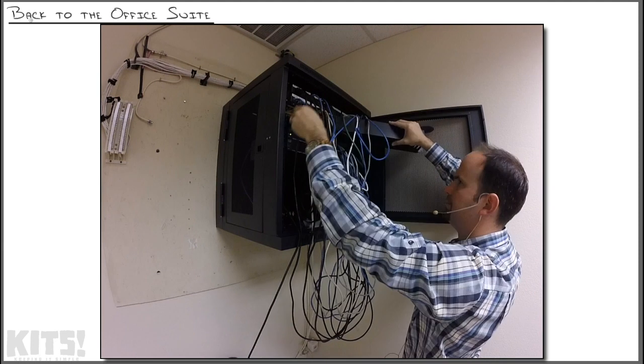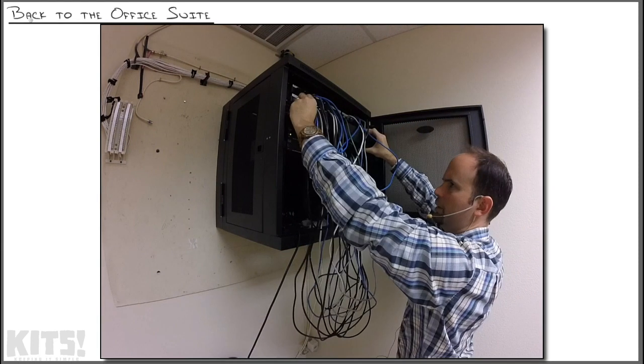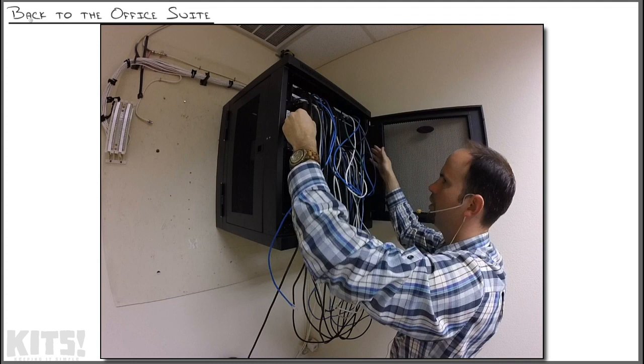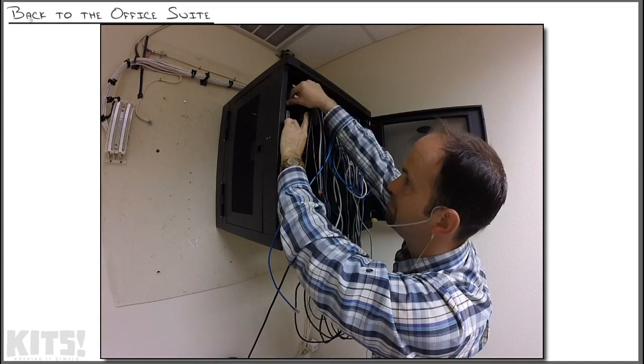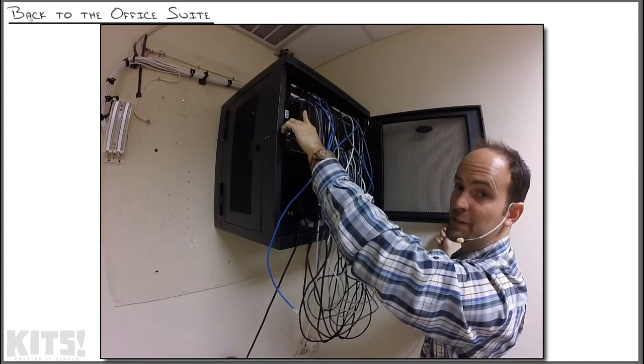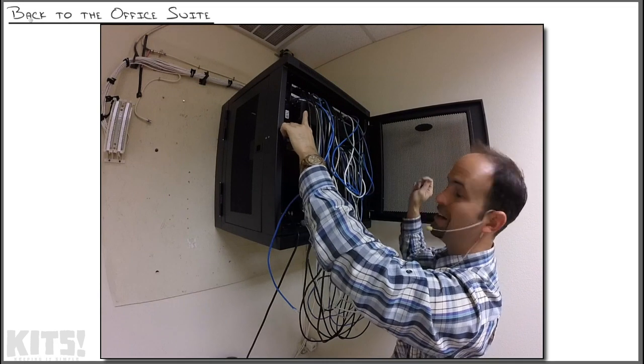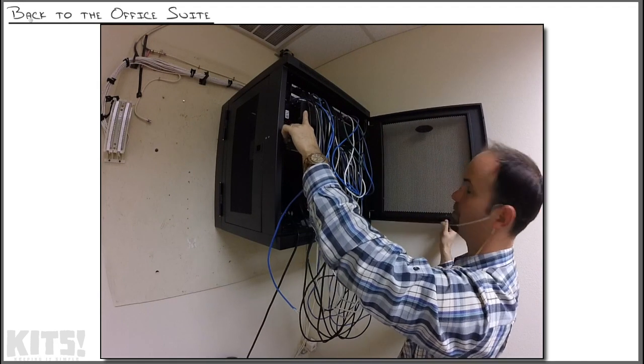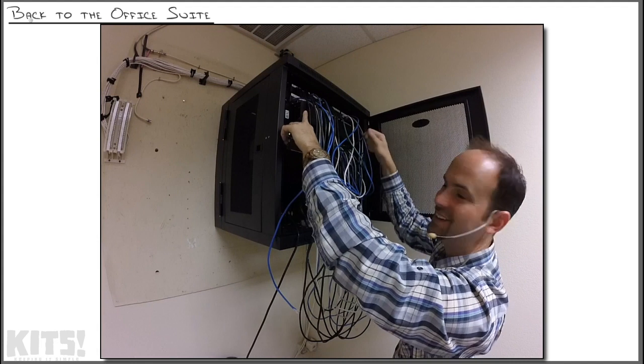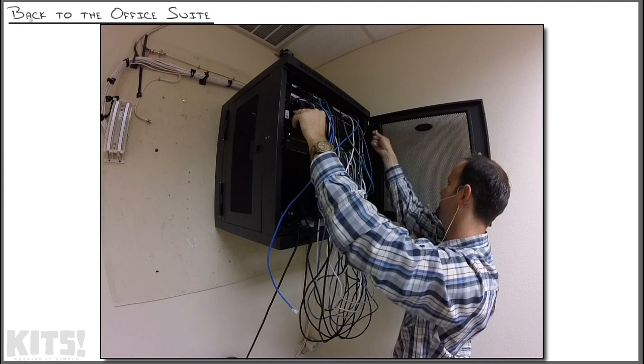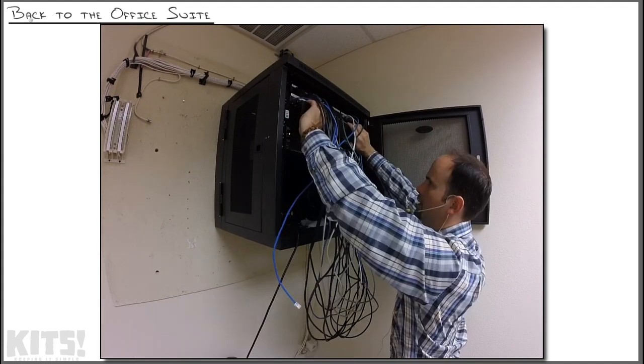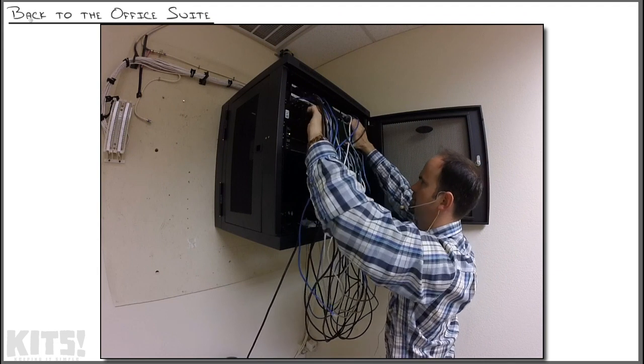Slide this guy in. I don't know what this little wire is doing here. There we go. Then we'll screw it in. You always want to make sure that your cable manager fits with the door closed. It's always a buzzkill to get everything in there, cables looking good, and then you go to close the cabinet door and find out this is too big. In this case, I've tested it beforehand. Good. Now we'll pop the plastic cover off.